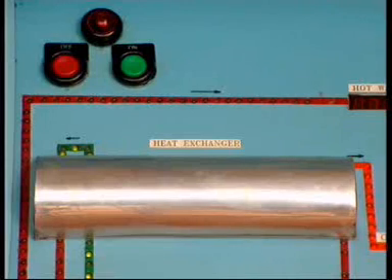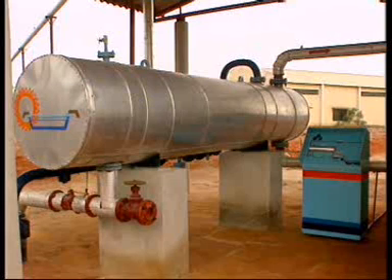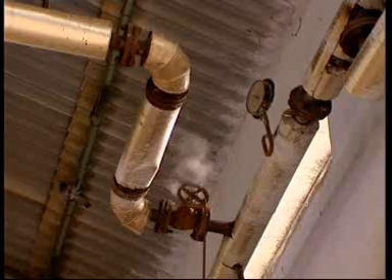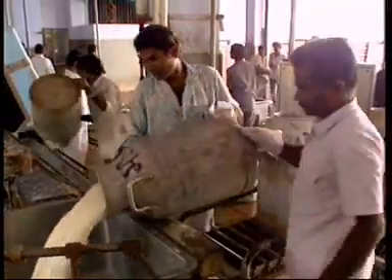The hot piped brine heats up normal water to about 70 degrees centigrade. With minimal loss of heat, it is carried to the boiler at the nearby catch dairy. The water is about 70 degrees hot when it reaches there, so the dairy needs much less lignite to bring it to a steaming 100 degrees for the pasteurization plant.